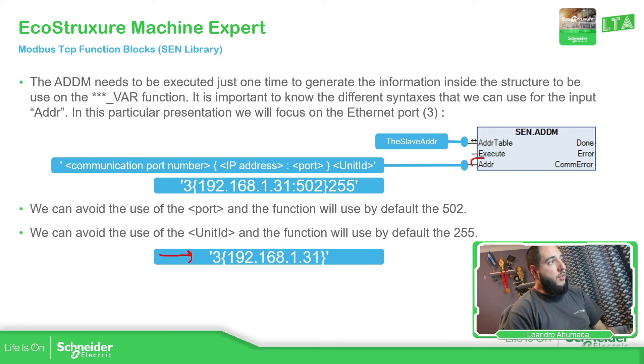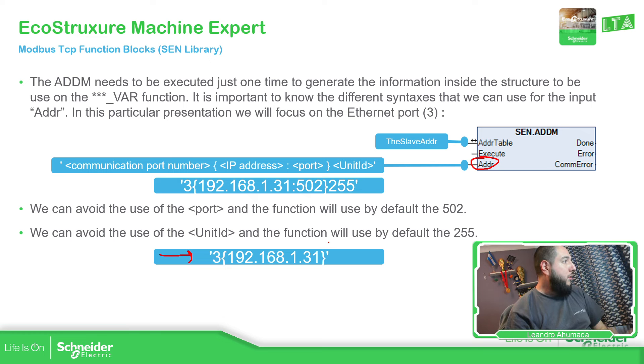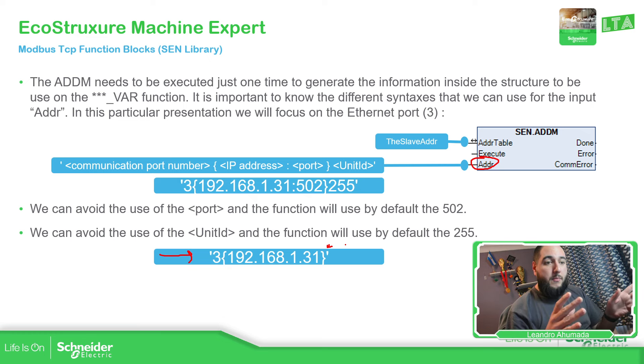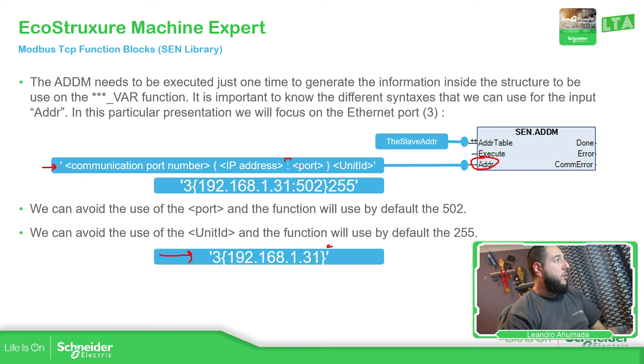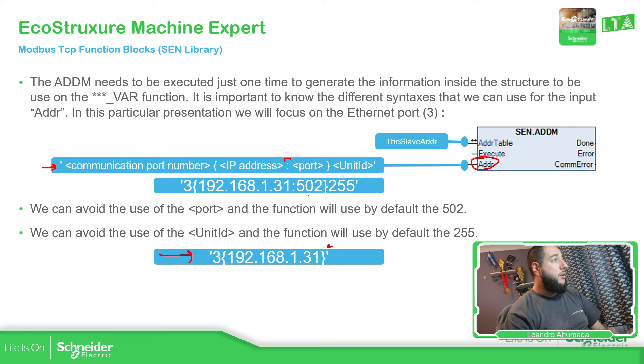The input of this one is a string, so we just need to use the single quotes in order to enter the port and the IP address. If you need a specific communication using a specific port and a specific unit ID, we have the possibility to define that. The generic format is: communication port number, IP address, two dots, and in case you want to use an additional port and unit ID next to it. By default, we have port 502 and unit ID 255.